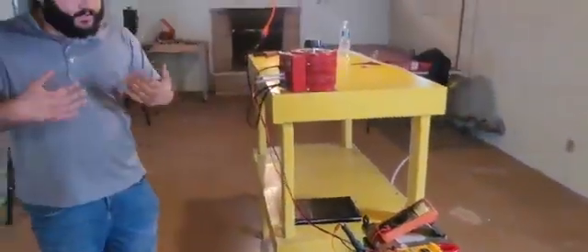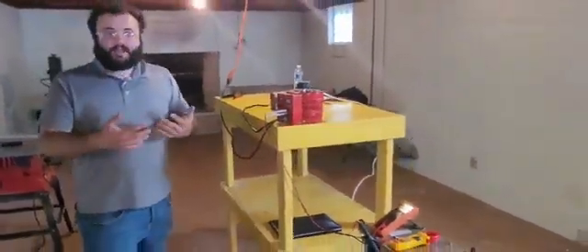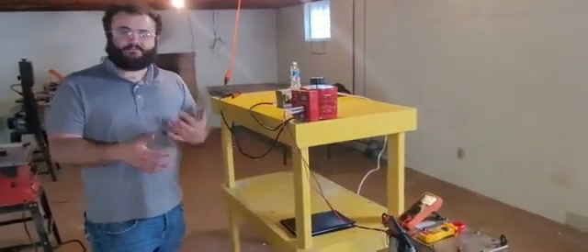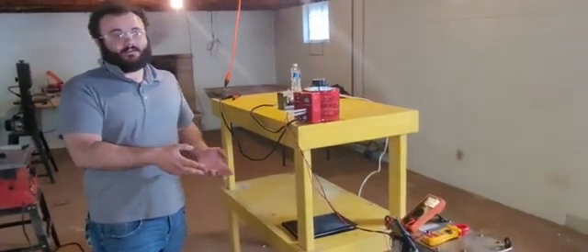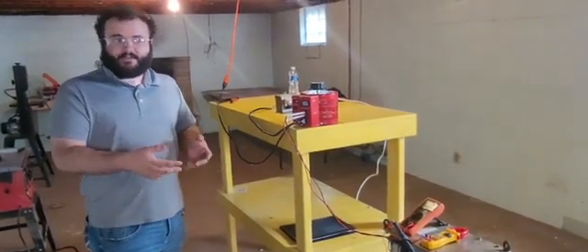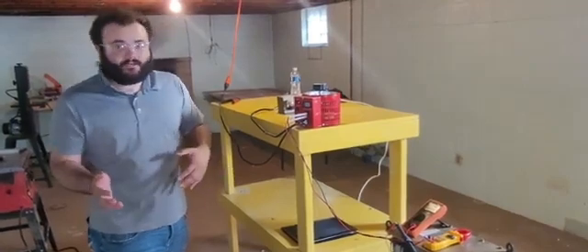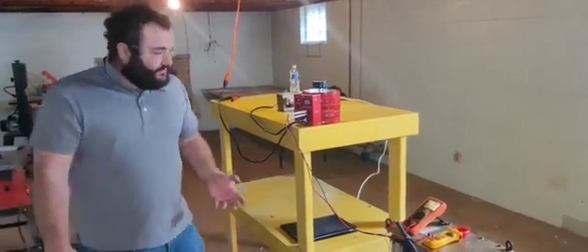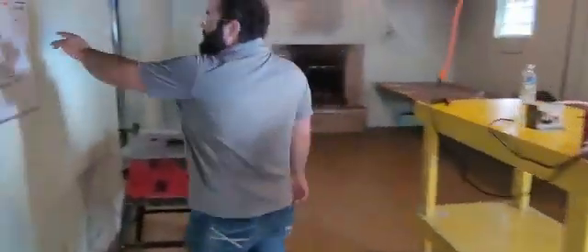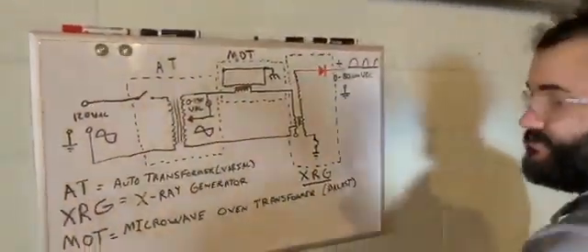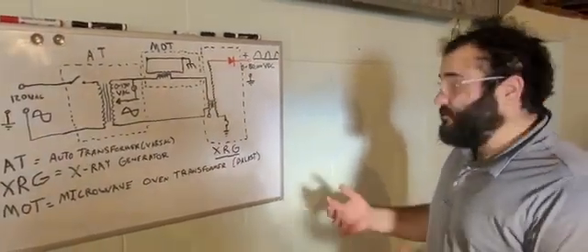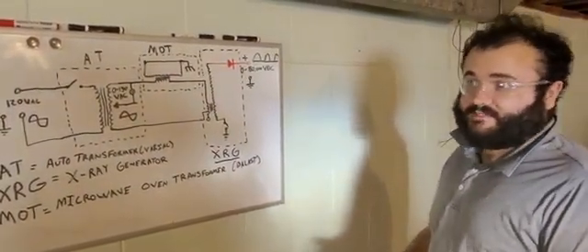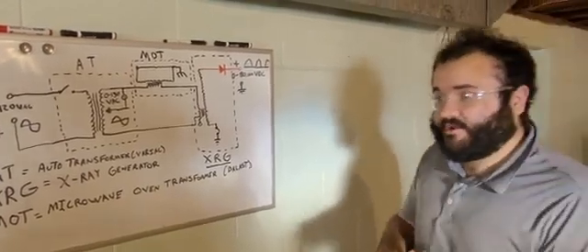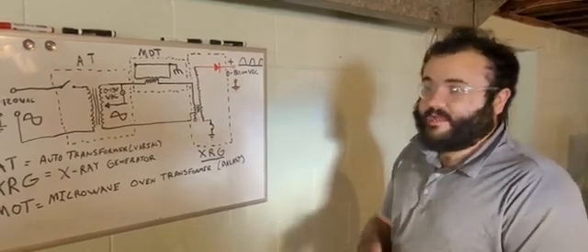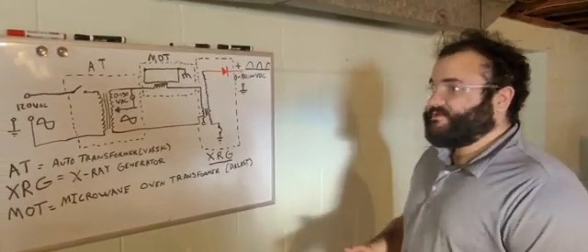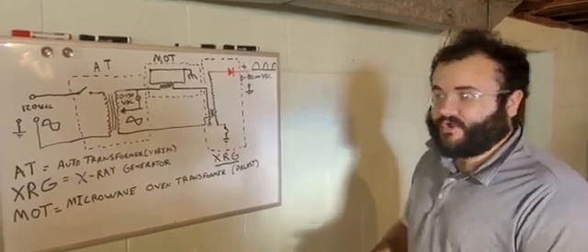Now you might be wondering, how could it be 80,000 volts when we only have such a small ratio? I mean, 0.6 to 32 volts seems like it would be about a 1 to 150 ratio on a transformer. But that's not the case. The reason is, come back here, this diode has a diode drop. Most silicon diodes have a forward diode drop of about 0.7 volts DC. However, to handle the sheer amount of voltage and current that's going through it, they had to make the diode much, much larger, and we're expecting about 400 to 600 volt drop across the diode.